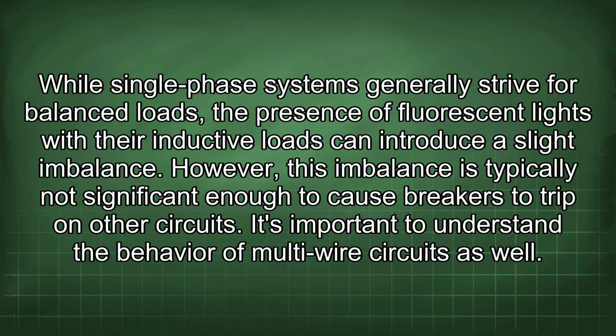While single-phase systems generally strive for balanced loads, the presence of fluorescent lights with their inductive loads can introduce a slight imbalance. However, this imbalance is typically not significant enough to cause breakers to trip on other circuits.